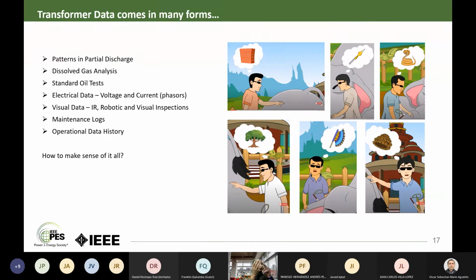Depending upon the sensors that you have: partial discharge sensors, dissolved gas analysis, which looks at all of the gas data in the transformer, because at the end of the day, a transformer has chemistry. There's oil inside, and the chemistry of the oil can tell you something about the transformer. There are standard oil tests that look at interfacial tension, moisture content, and other things. There's electrical data, voltage, current, phasor measurements. There's visual data, infrared imaging, robotic and visual inspections. There are maintenance logs, which is unstructured data.